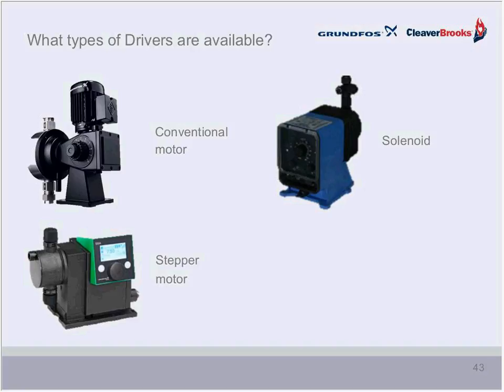The solenoid driver is essentially two magnets that attract and repel each other as power is applied and removed. Along a shaft, this causes the reciprocating motion of the diaphragm. These pumps are significantly less expensive, with limitations on performance at the low range. Now, steppers are an advanced type of motor, a brushless DC motor, but with pulsed power input. These give complete control over the suction and discharge strokes independently, and an extremely accurate turn-down range of the pump. All driver types are applicable in steam boiler systems. Selection is dependent on a wide variety of factors, including the pump size, accuracy, cost, and others.